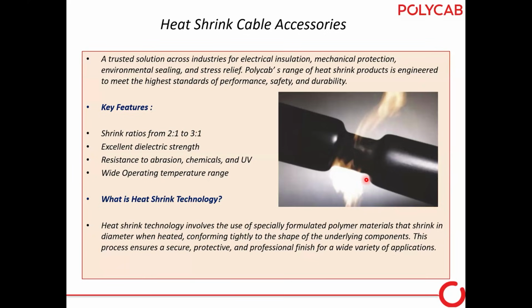Heat shrink technology is extensively used because this technology has proven how reliable it is. It's a trusted solution across industry, in terms of electrical insulation, mechanical protection, environmental sealing and stress relief. That's why heat shrink accessories are widely used in India. Key features: heat shrink accessories come as tubing, heat shrink tubes. Shrink ratios are generally 2:1 and 3:1. It has excellent dielectric strength, and resistance to abrasion, chemicals and UV. Even if you use these heat shrink tubes in a chemical area, or put soil or anything on those joints, they have excellent resistance properties.